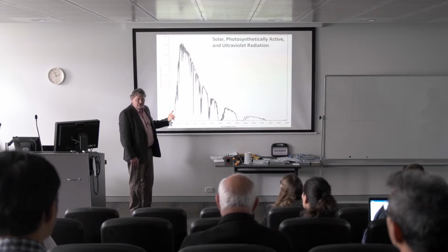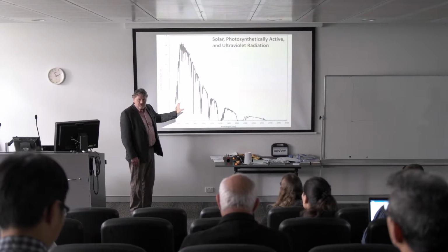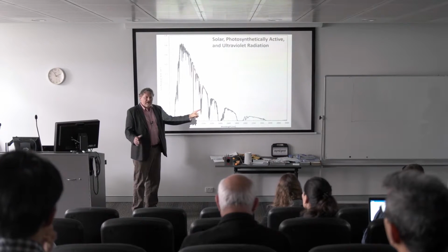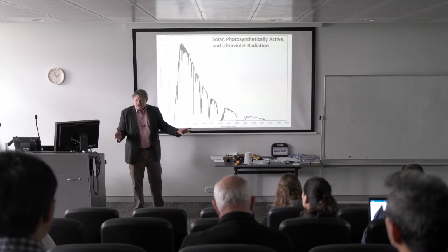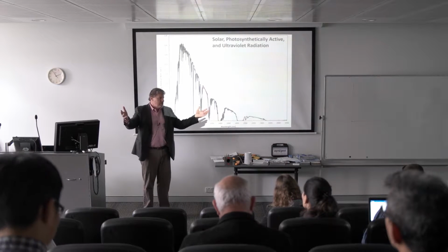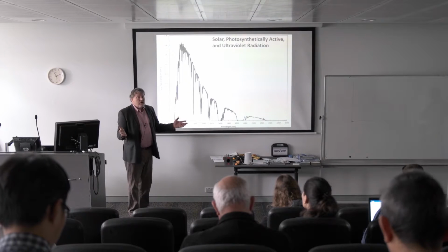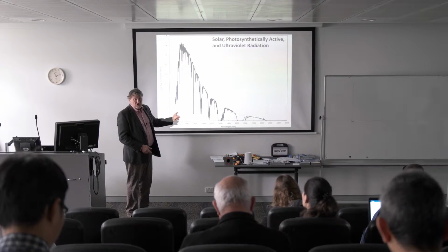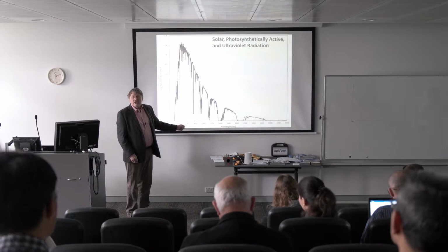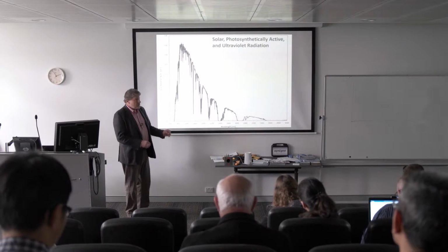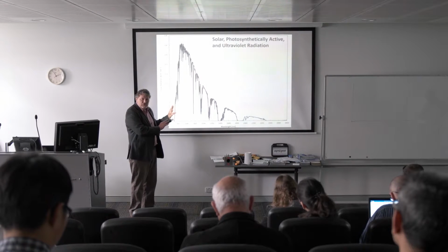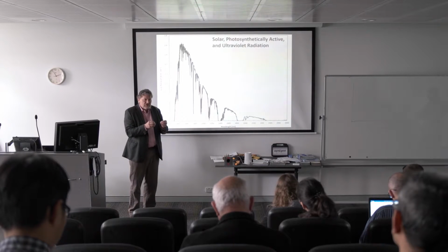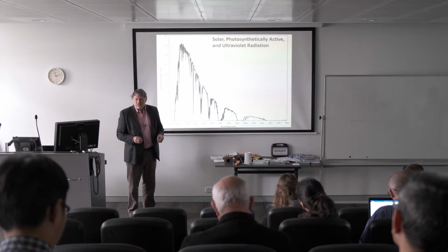But silicon cell pyranometers subsample this spectra and predict the rest. And we do that all the time in science. We subsample things and then we predict the whole. And that's fine, but subsampling changes, the spectra changes with atmospheric humidity. So what I'll show you is the data on how atmospheric humidity affects this spectra and how it affects the accuracy of our silicon cell pyranometers.